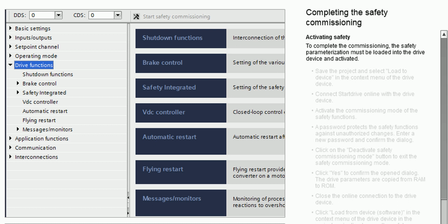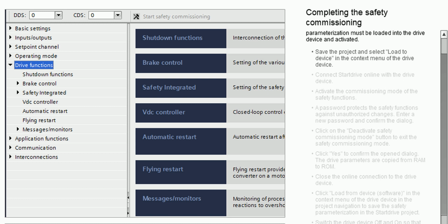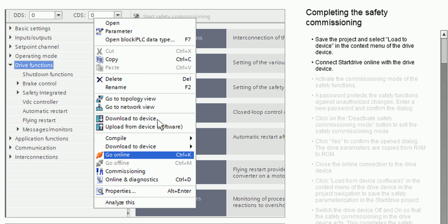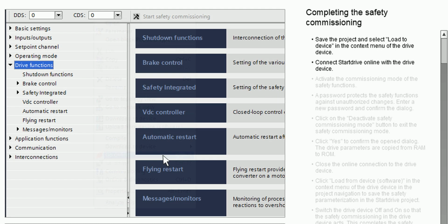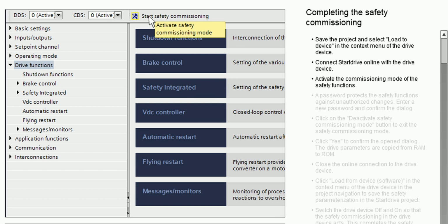Activating safety. To complete the commissioning, the safety parameterization must be loaded into the drive device and activated. Save the project and select Load to Device in the context menu of the drive device. Connect Startdrive online with the drive device. Activate the commissioning mode of the safety functions. A password protects the safety functions against unauthorized changes. Enter a new password and confirm the dialog.